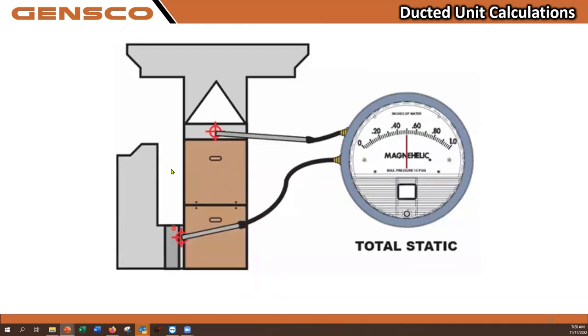The system effect has to do with how air actually enters the blower and can be caused by things like ductwork fittings right next to the furnace, one side tap, or insufficient space, straight duct horizontally before it side taps in order to allow it to enter the blower uniformly. They can all have an effect on the actual air that's coming out of the unit versus the blower chart. But to measure static pressure, you want to be as close to the blower as possible and between the blower and the filter, and then on the exit side of the unit.